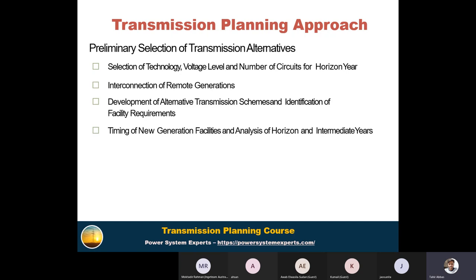We will discuss why we select a different voltage level for transmission. Like if I'm selecting HVAC 500 kV, why? That depends upon the power evacuation and the loss and the corona and all other factors that we will discuss at the extra high voltage level. And similarly, the interconnection of remote generation. So this is also most important. I'm connecting the southern generation towards the load center. So that's a very important parameter also. Where and at which point I need to connect that remote generation. Either I should directly import towards the load center, or I should evacuate simply from the southern part towards our load center. So this basically depends upon the analysis.